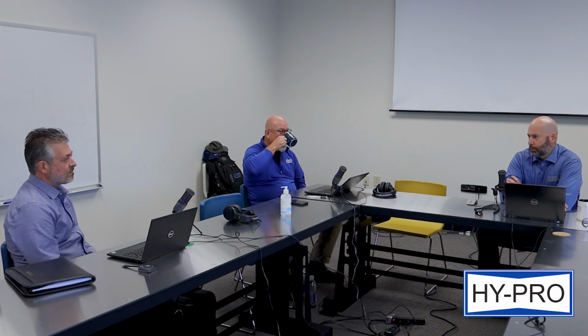So when you're looking at different technologies for an application, one of the things you always want to consider is, what are we going to have to do to keep this thing running? Because we're buying a piece of equipment to fix a problem. Are we adding another problem? The way I look at it, if you're on a nuclear aircraft carrier, and you've got a guy that all he does is take care of the centrifuge, it'll probably work fine. And it'll do a good job. In an industrial environment where resources are limited and people are pulling multiple duty and people are stretched, I don't see it as an effective tool anymore.